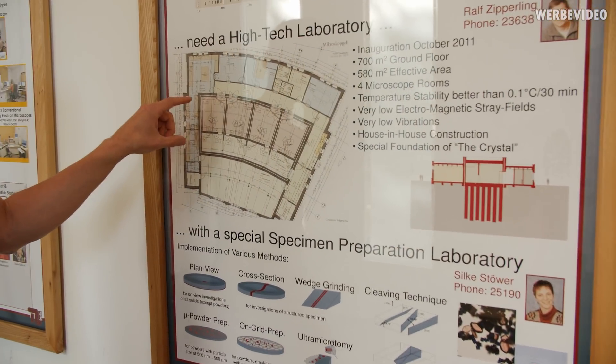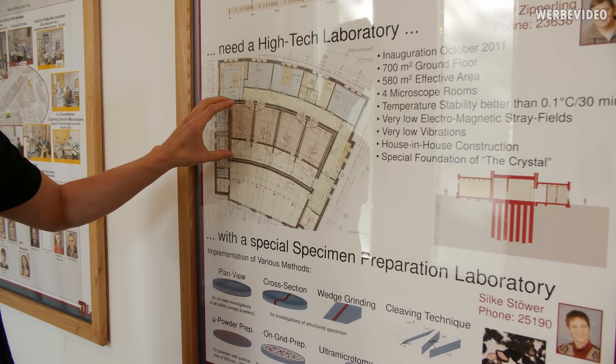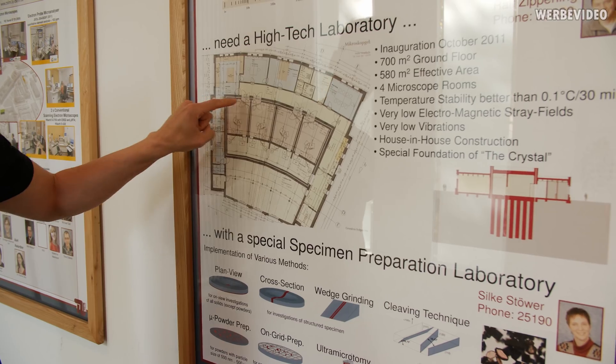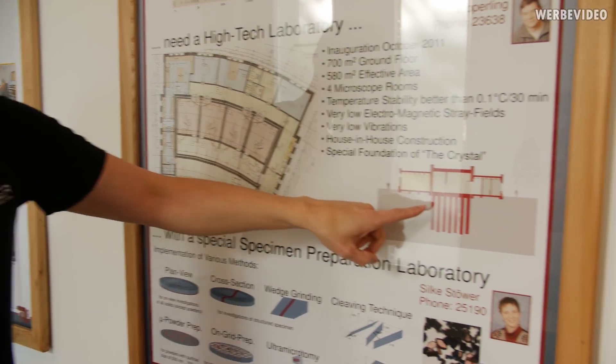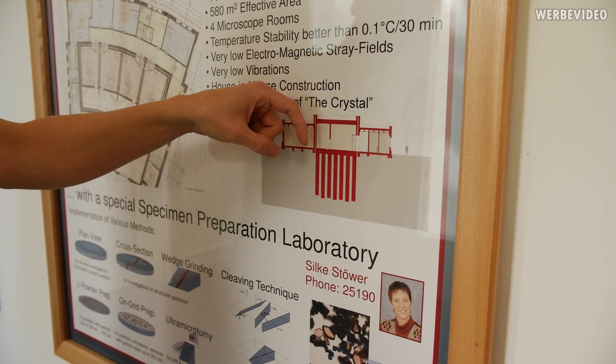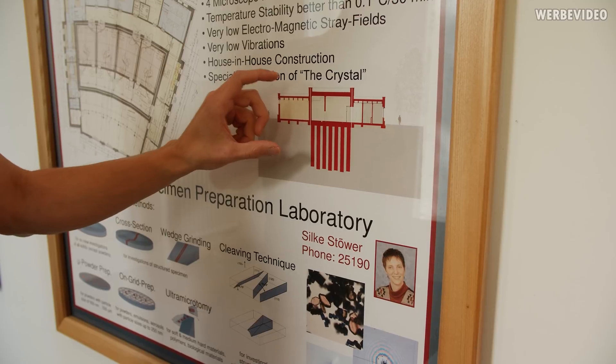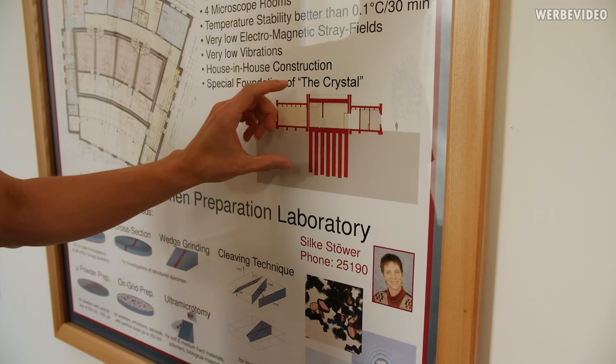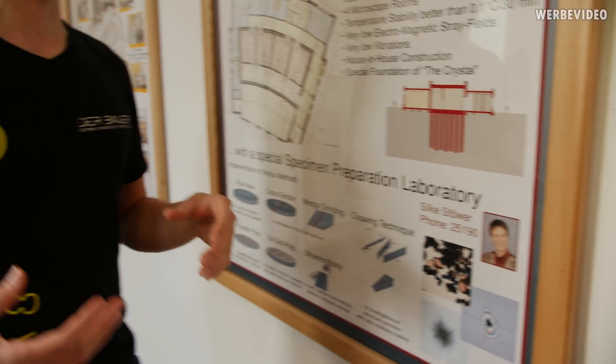Basically we have two buildings in one. There is this center building right here which is separated from the outer one and you can see there's this gap in between. If we take a look on the right side we have concrete pillars going into the ground by about 10 meters. This was required to have a disturbance-free environment from the outside, otherwise we would have vibrations inside the building which would make it impossible to take those kind of shots with the microscopes.